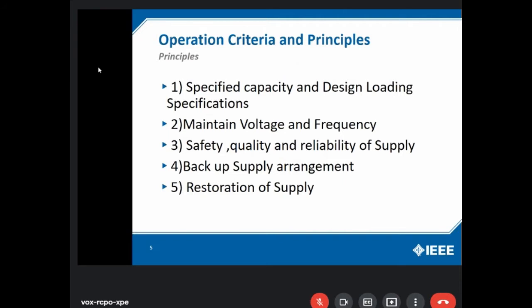Operations criteria and the principle. We'll first be discussing the principle. Number one is the specified capacity and the design loading specification. Number two, maintain the voltage and the frequency. Number three is the safety, quality, and reliability of supply. Number four is backup supply arrangement. Number five is restoration of supply.